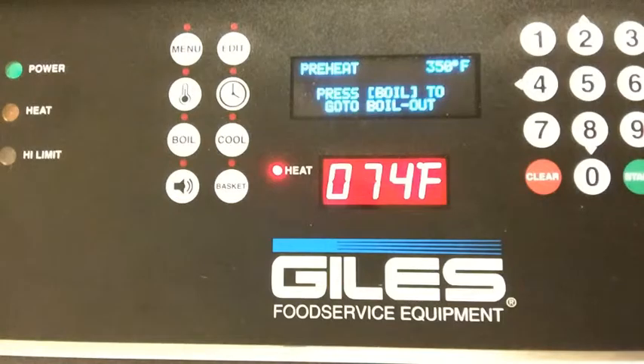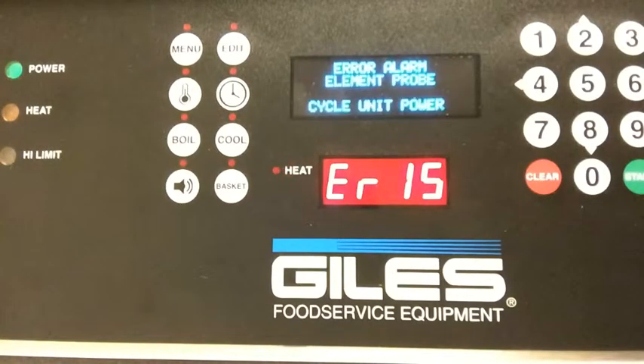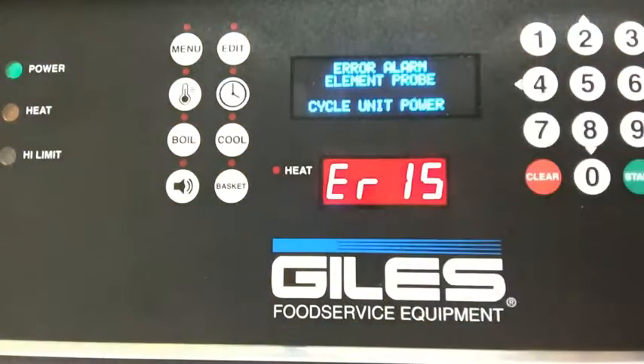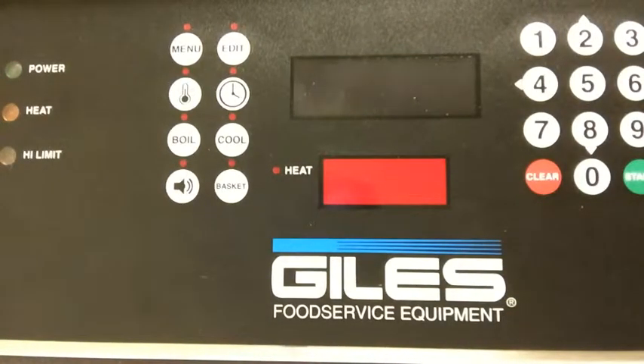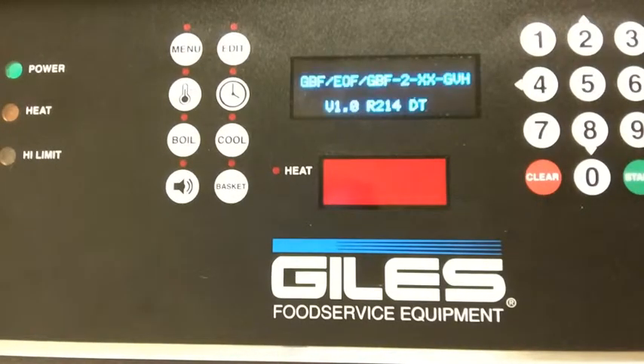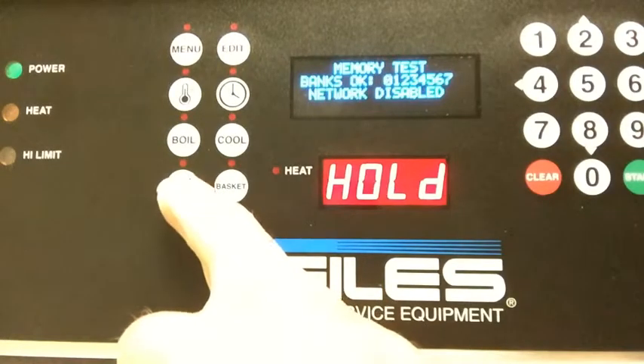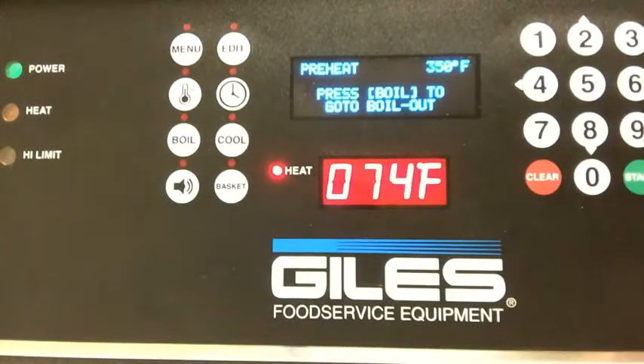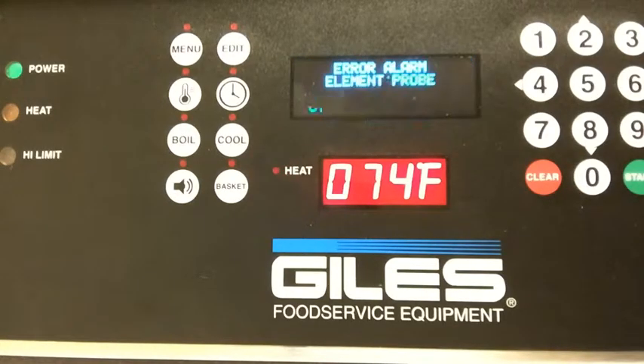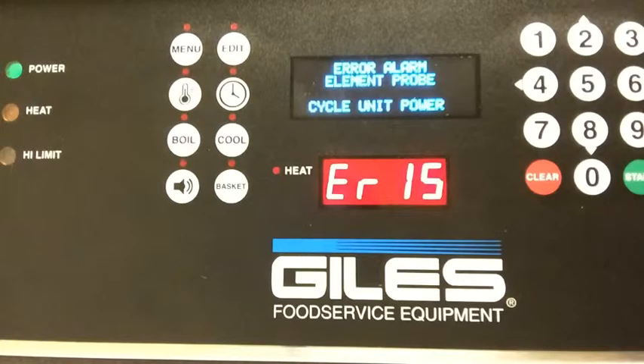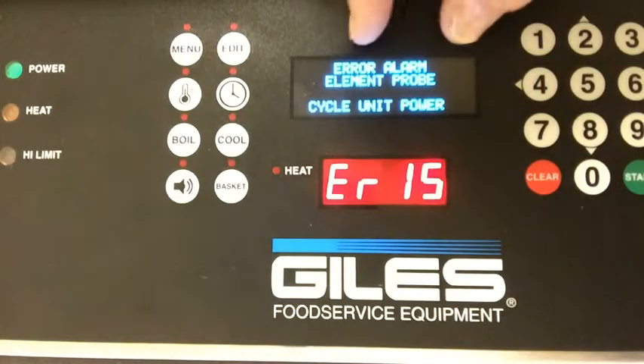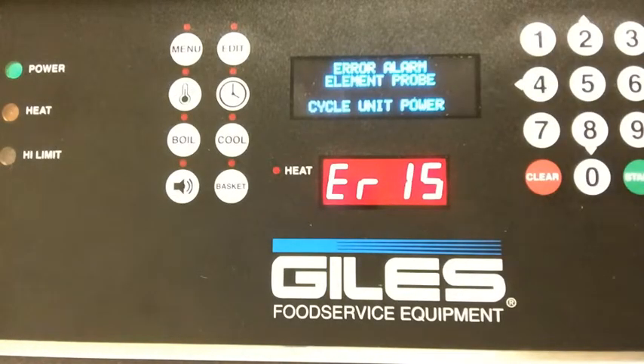Now if we were to have a problem with our element sensor, we would get an alarm, and that alarm would actually tell us that's what it is, and that we would have to cycle. Here we are, error alarm, element probe, cycle unit power, error 15. Now if I cycle the power as it suggested, the unit will come back up. Of course it's going to give me that alarm, power failure. If I press the preheat, it's going to try to heat. Now if I have not corrected the issue, it's going to come right back. So normally what that means is that I have a broken lead. I have a problem with getting any kind of an input. It's not seeing that element sensor. So we need to go ahead and try to figure out what that problem is.